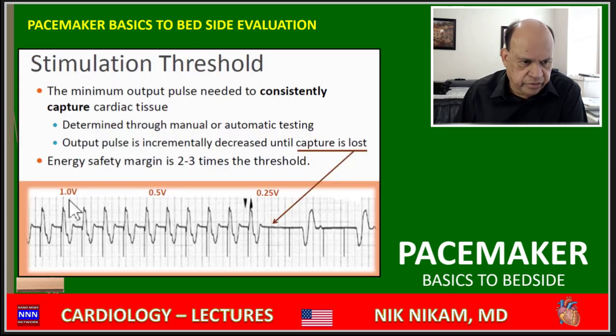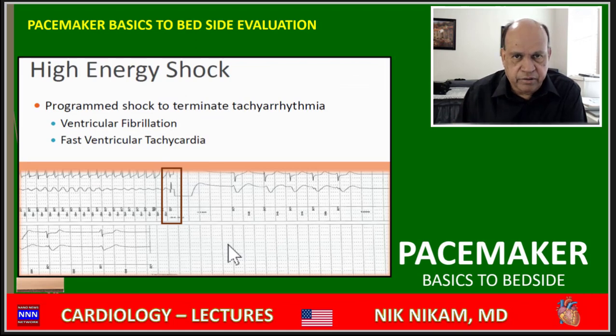As you can see, at 1 volt it was pacing good, at 0.5 volts it was doing good. When you go to 0.25, it drops - the capture is lost, meaning the energy is too weak to activate the ventricle. To kick the ventricles you need certain energy, and 0.5 is the reasonable energy - you're not using too much, because using 1 instead of 0.5 drains the battery twice as fast. Another function of the pacemaker is electrical shocking, or intracardiac defibrillation.